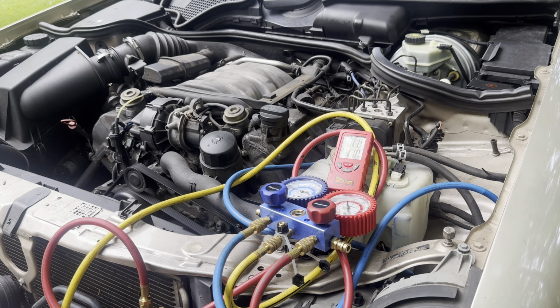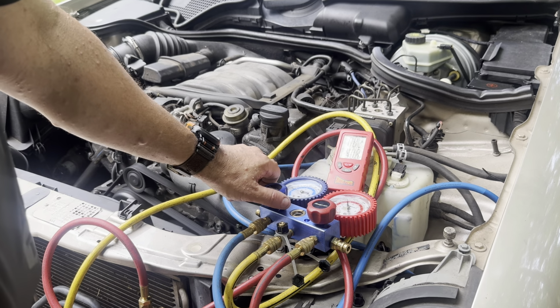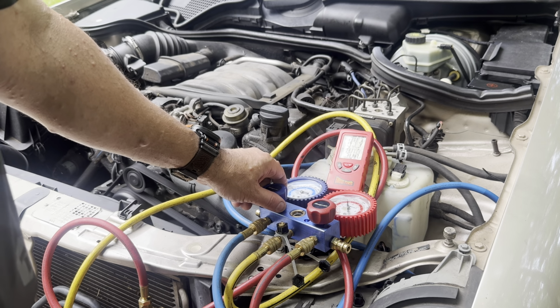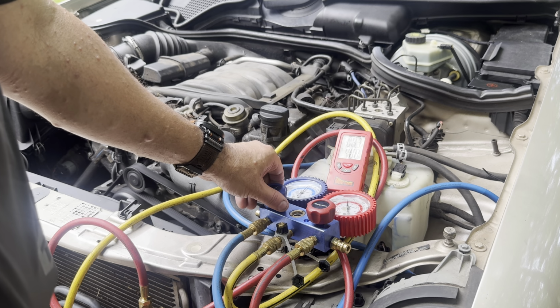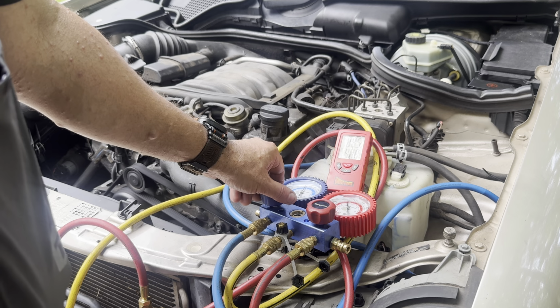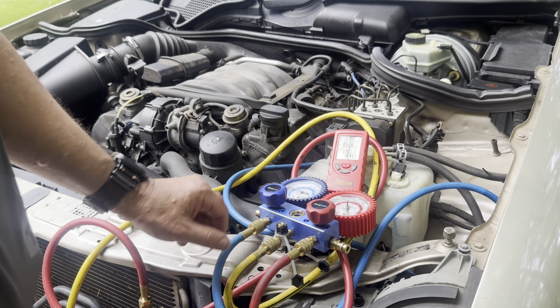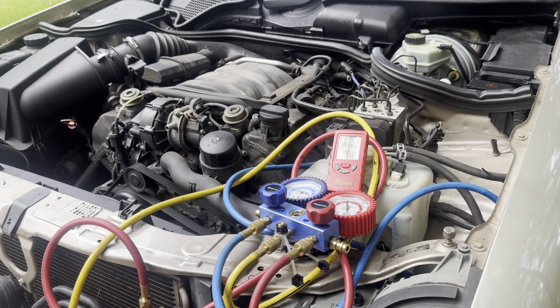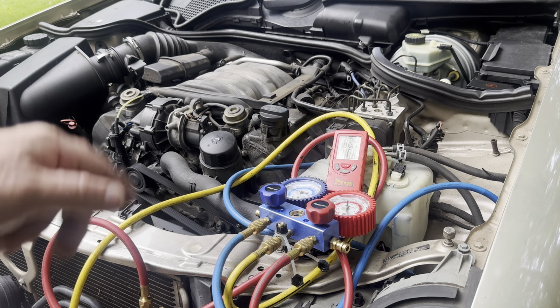So right now we're 41 degrees and we're running just below 30 on our pressure. So we're going to get a little bit more refrigerant in there. We're down to 40.8.